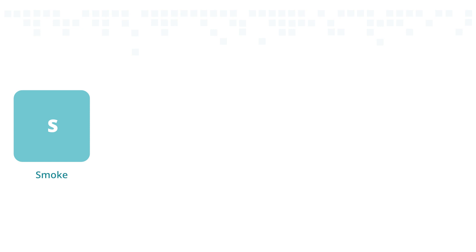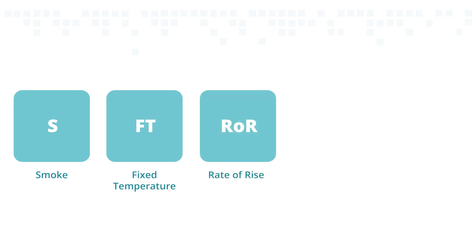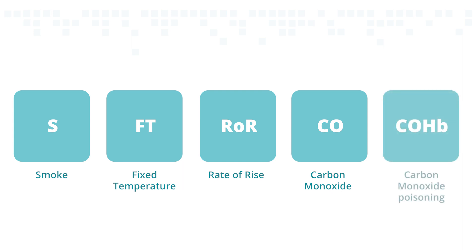The modes are represented by mode strings — characters and symbols showing which sensing elements are active and in which combinations. The letters represent the type of detection: S for smoke, meaning the smoke chamber is active; FT, meaning the heat elements are active and set to alarm at a set temperature; ROR represents the same heat elements but set to activate after a rise in temperature over a set time; CO represents the CO sensing element; and COHB — the chemical symbol for carboxyhemoglobin — is used for modes that track CO density, giving a warning about the threat of CO toxicity and carbon monoxide poisoning.